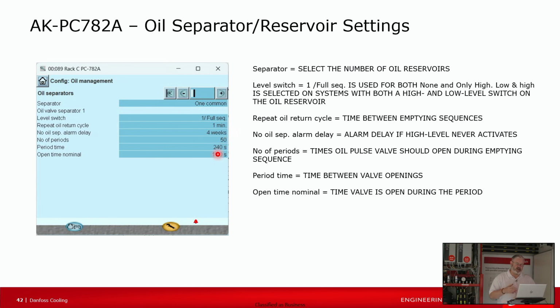And if you were dealing with that on a startup, having oil issues, if you were starving for oil, you might consider adjusting this nominal opening time. Increase that a little so that you're trying to get more oil out of the separator. So those are kind of our three options: high level switch only, high and low level switch, and then timing only. I hope that answers your question about the oil.